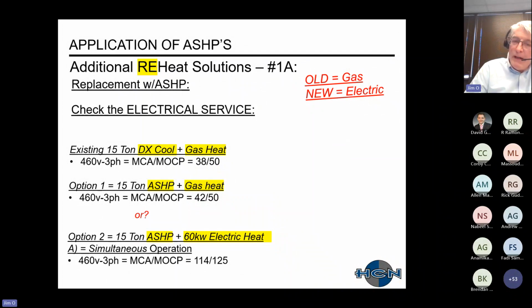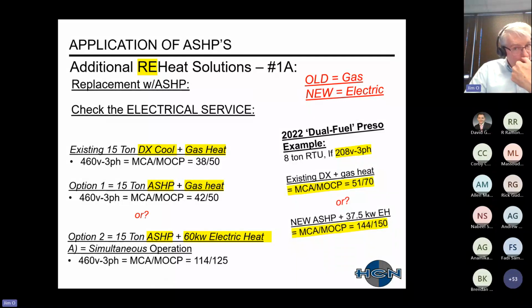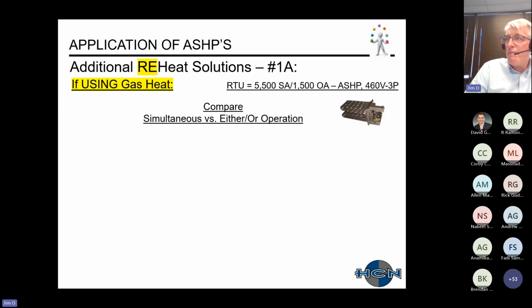It's much larger than the existing service. And then I did, I don't want to say a sister presentation, but a dual fuel presentation back before this one. And I did have an example of an 8-ton unit that had a similar situation, where the existing unit had that electrical service for a gas heat, and then switching to an air source heat pump plus electric heat is much larger.